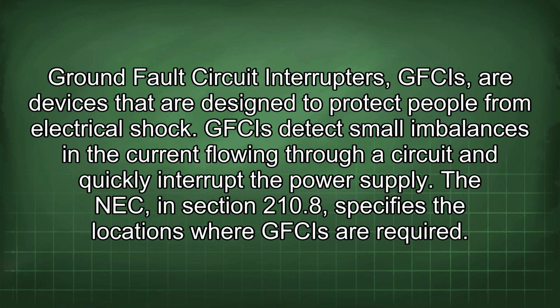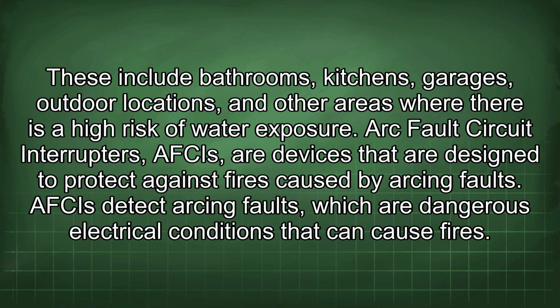Ground fault circuit interrupters, GFCIs, are devices that are designed to protect people from electrical shock. GFCIs detect small imbalances in the current flowing through a circuit and quickly interrupt the power supply. The NEC in section 210.8 specifies the locations where GFCIs are required. These include bathrooms, kitchens, garages, outdoor locations, and other areas where there is a high risk of water exposure.